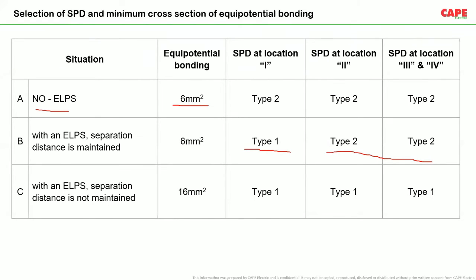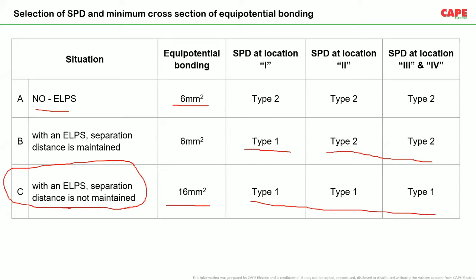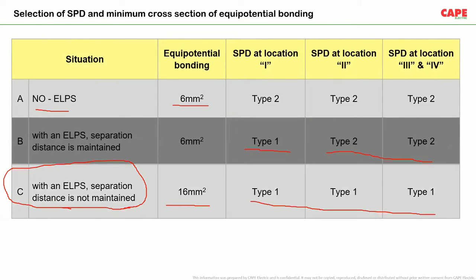And if the building is with external lightning protection, and separation distance is not maintained, which is generally the case in all the cases we do, no separation distance is maintained. The lightning protection air termination and the frame of the solar PV are often connected, or it is running very close by without calculating the separation distance. Under that condition, the minimum equipotential bonding conductor must be 16 square millimeters, and you should use type 1 SPD in all the locations. It is not a type 2 SPD, it is type 1 SPD. So you have to be careful in this particular case.